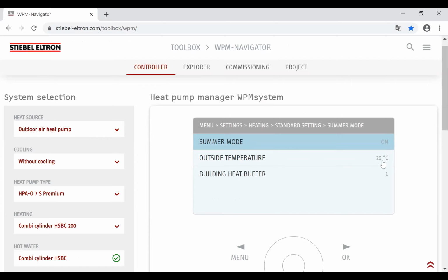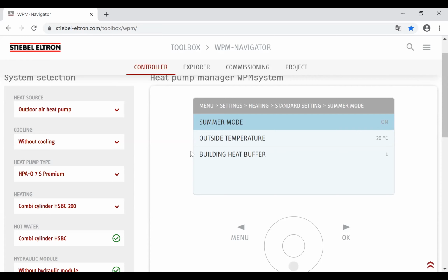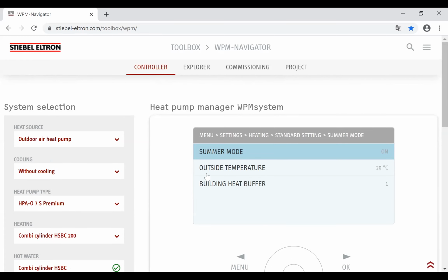So in the most simplistic way, just using Stiebel control only running from the WPM, you could have a system with 1 manifold underfloor heating, no controller in the house at all, and the temperature outside starts to drop below 20 degrees. The unit says, all right, it's getting below 20 degrees, let's start up. Away it starts, and then the temperature keeps dropping, and it says, righto, it's getting colder and colder outside, let's start lifting our temperature. And it could run purely on a fully automated weather dependent mode. Very, very simple. A lot of people set them up like that.